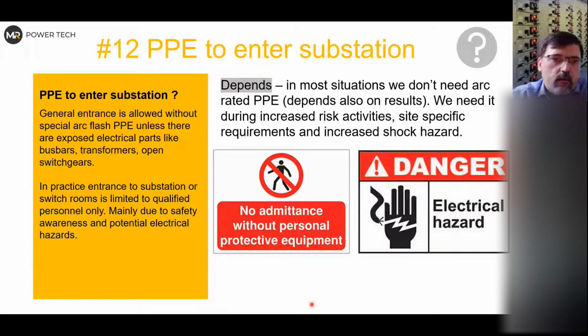When we talk about arc flash related hazards, just to enter the room, normally it's not required to have any arc flash PPE. So let's say, I can tell you a story. You just go into the substation, a low voltage substation, and everything is fully enclosed, normal operation. So you don't have any exposed bus bars or transformers inside. So you just want to go there, I don't know, have a look if you have an extinguisher there and the date is okay. So do some simple inspection. And just to enter the room, generally you don't need any arc-rated PPE. But it might be that you have already identified very high incident energy and you decided as a site that your minimum PPE, just for daily work, is 12 calories per square centimeter, then you already have it.